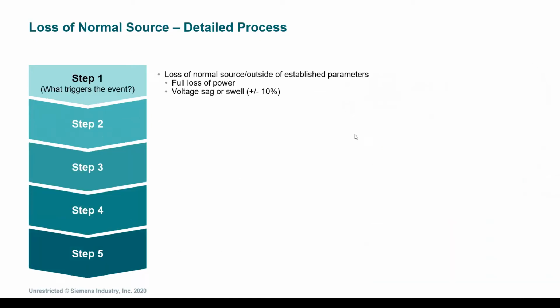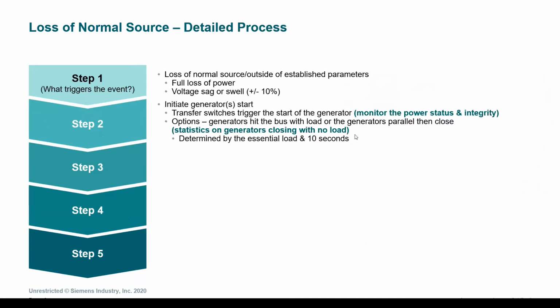Going into this in further detail, the first question that we ask is, what is triggering the event? Typically, they would fall under a full loss of power or a voltage variation outside of what we would like to see for our normal voltage. Step 2, the generators are initiated a start signal by the transfer switches. The transfer switches are obviously monitoring the power status and the integrity of the power that's coming in. A couple different ways that this can be done is the generators hit the bus with the load, or the generators parallel and then close and the load is transferred over.